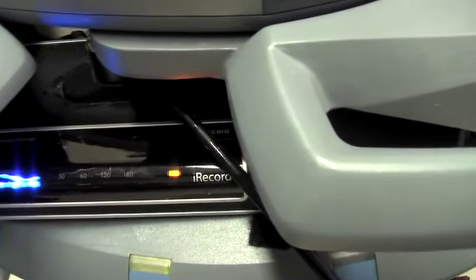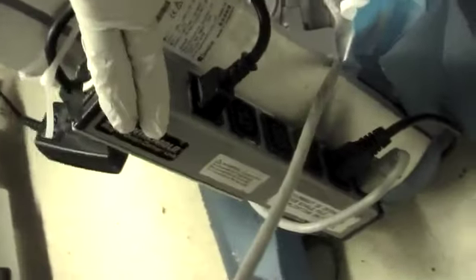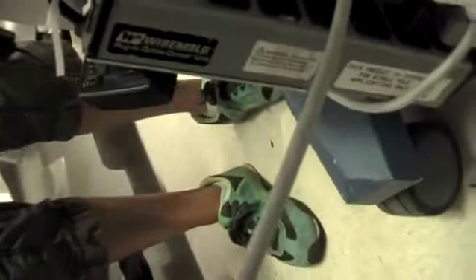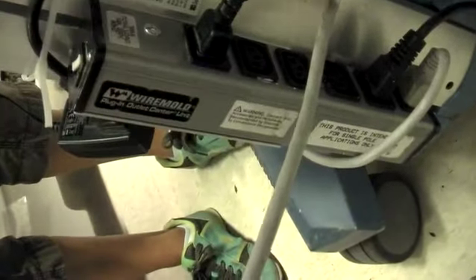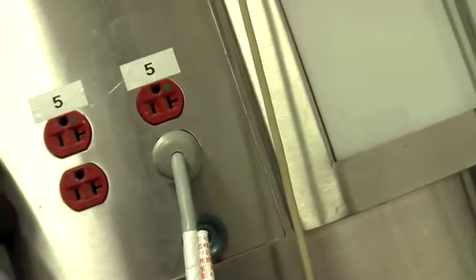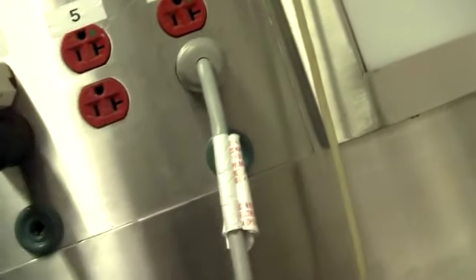So, moving along to troubleshooting some of the wiring in the back of the machine. This is your main power strip. It attaches to this gray cable here, which is now wrapped around the machine, but this needs to plug into the wall, both for the machine to be charged and also for the iRecord to have power. So that's the first place I look. When people call me from home and the machine doesn't work, I check to make sure that this is plugged in right here, and that all these other two connections are also plugged in.